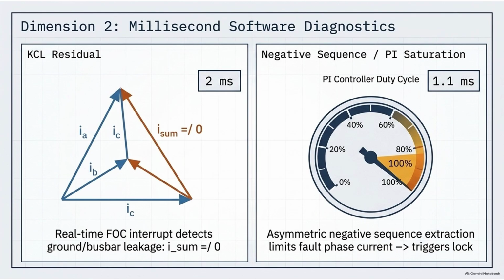The software monitors that sum, and if the residual current exceeds a specific threshold, it can confirm a ground short in just 2 milliseconds. That's fast. It is. It also monitors the internal control loops for PI saturation. If there's a slight creeping internal short in the motor windings, the proportional integral controller will have to push harder and harder to maintain the requested torque. Oh, I see. If the software sees the controller sitting at a 100% duty cycle for 1.1 milliseconds, meaning it's giving maximum effort just to keep the system stable, it flags a confirmed asymmetry fault.